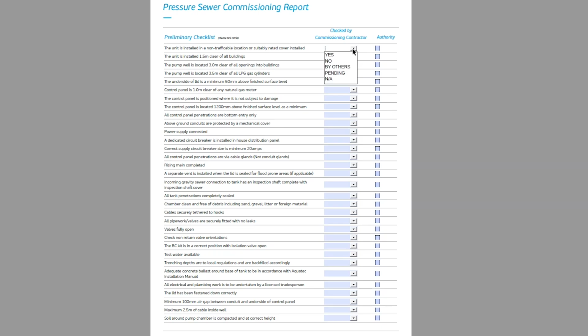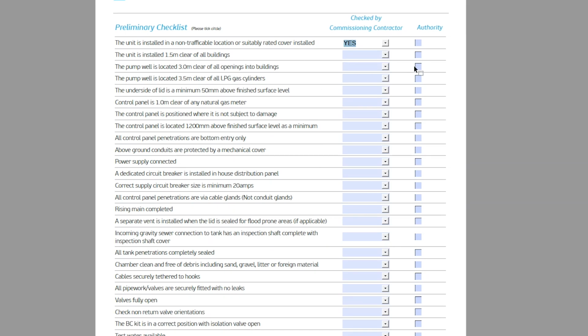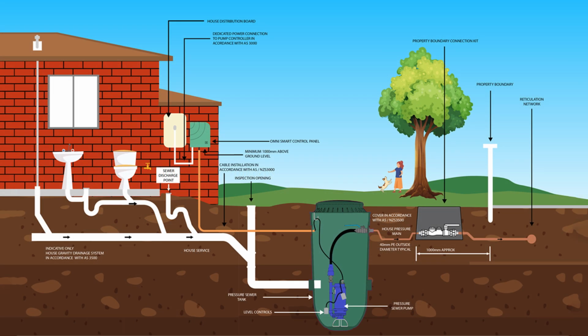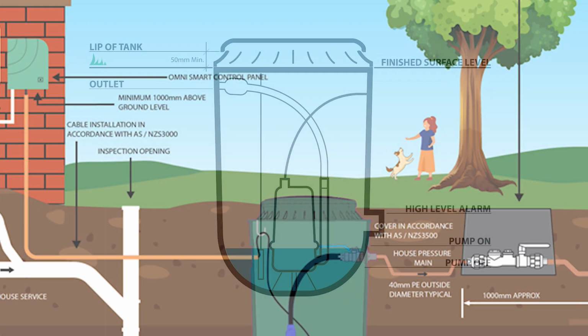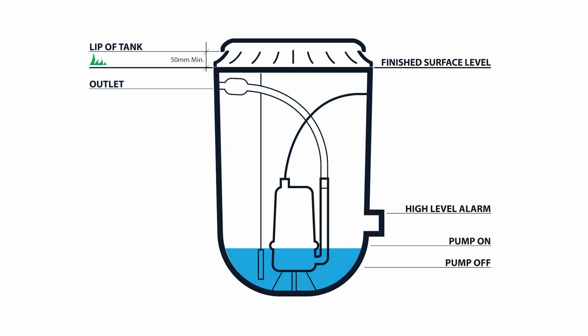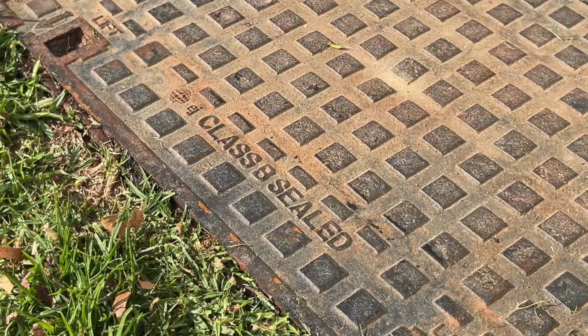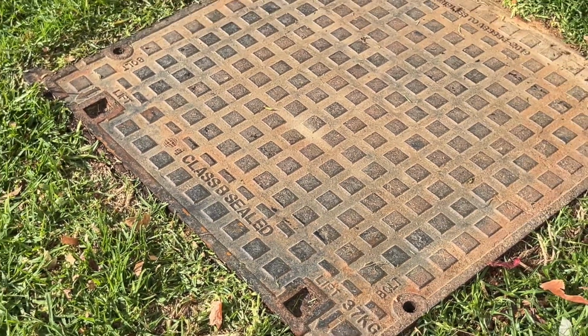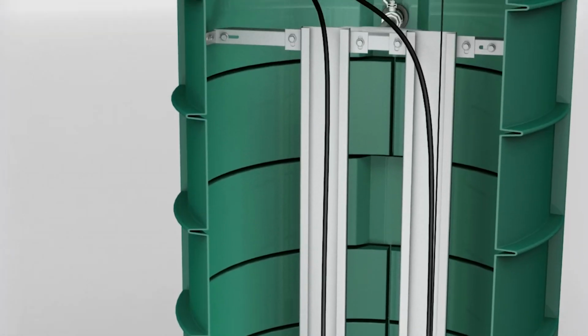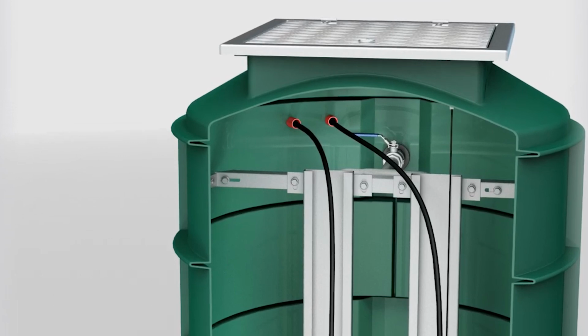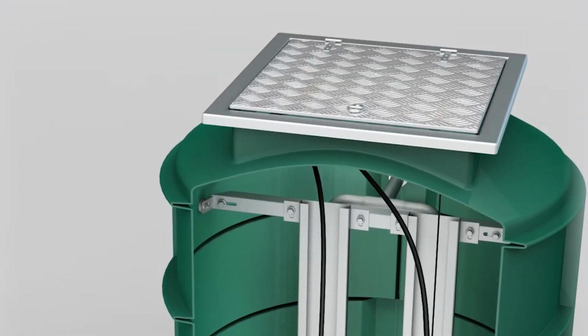A lot of the points listed on this page are simply good practice. Others come straight from building codes. One of the most important things to check is the minimum clearance of 50 millimeters above the finished surface level on a self-venting lid. There's not really a maximum to this dimension, just what's practical. Alternatively, if you've got a sealed lid, it can be flush with the finished surface level. What we're trying to eliminate here is stormwater ingress from a deluge of rain.